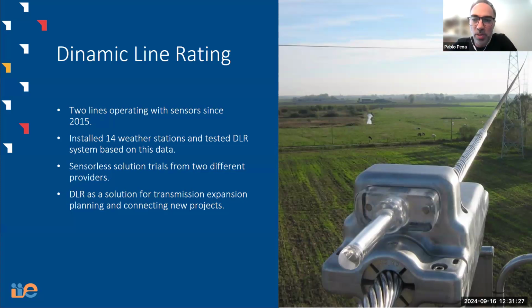Now, let's shift to the real world experience. Since 2015, we've been operating 2 lines with dynamic line rating sensors in a pilot project, along with a trial of a sensorless solution and the installation of 14 weather stations, and tested a dynamic line rating system based on this weather data. Furthermore, we have adopted dynamic line rating as a solution for transmission expansion planning and for connecting new projects. For example, the new Google data center that will be in service in a few years.